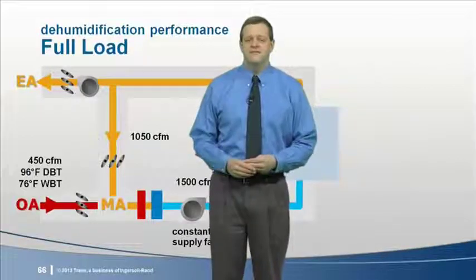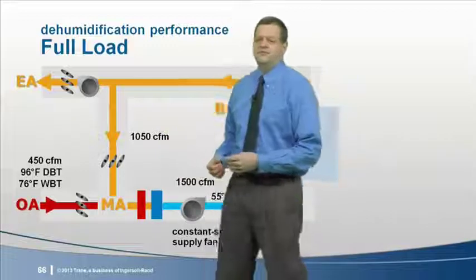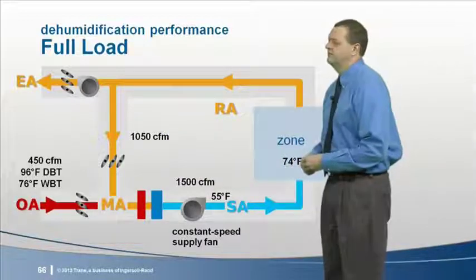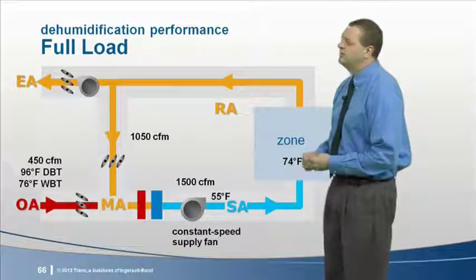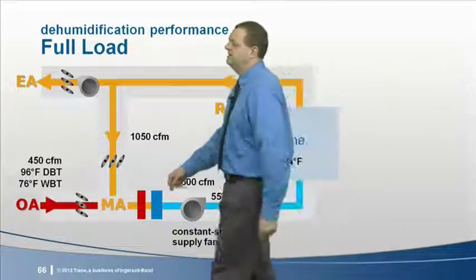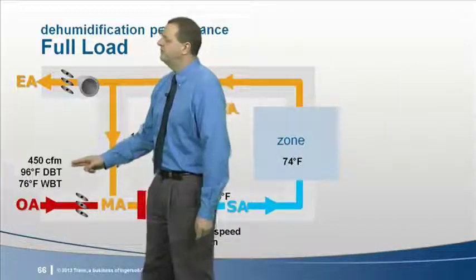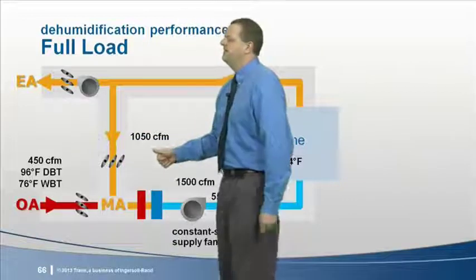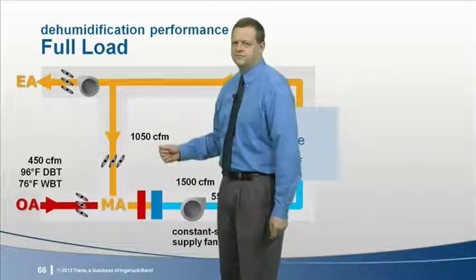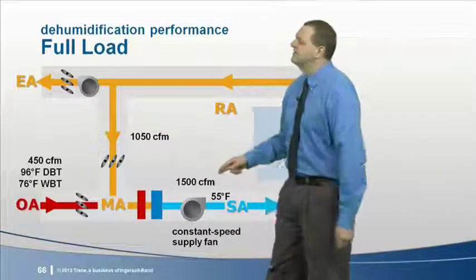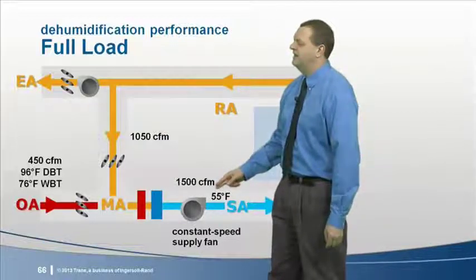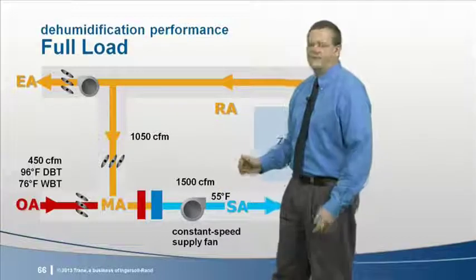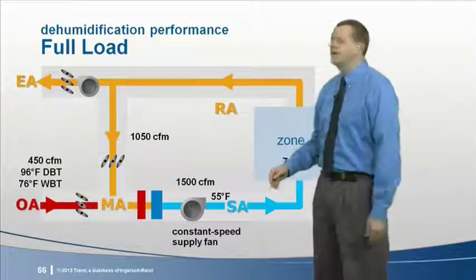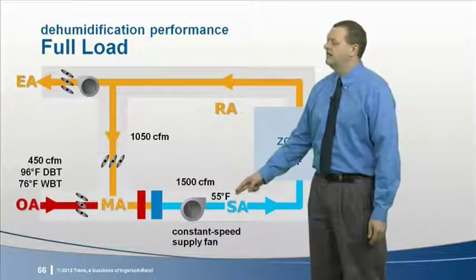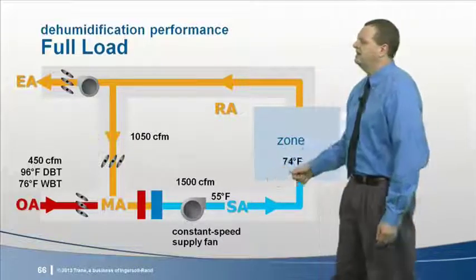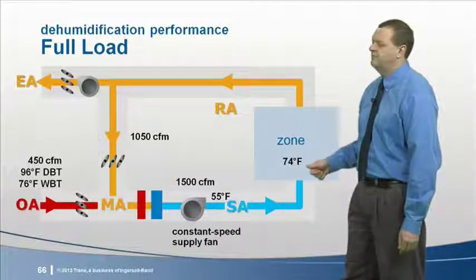To demonstrate the dehumidification benefit, here's an example system serving a single classroom in Jacksonville, Florida. At the cooling design conditions for this location, this system mixes 450 CFM of outdoor air with 1,050 CFM of air recirculated from the zone. Then it delivers this 1,500 CFM of supply air to the classroom. At this full load condition, the system cools the air to about 55 degrees to offset the sensible cooling load in the zone, maintaining zone temperature at the desired set point of 74 degrees.